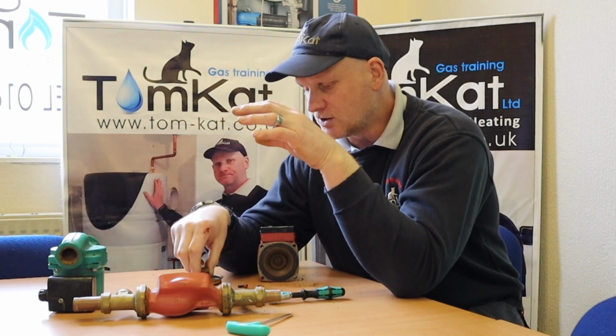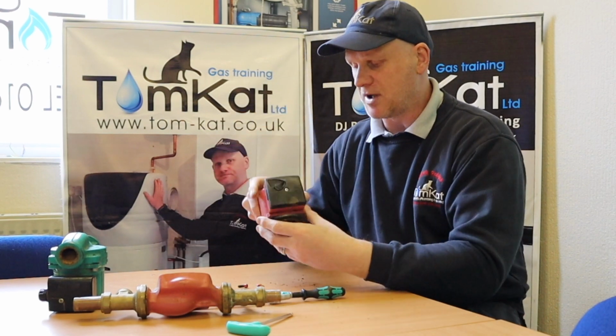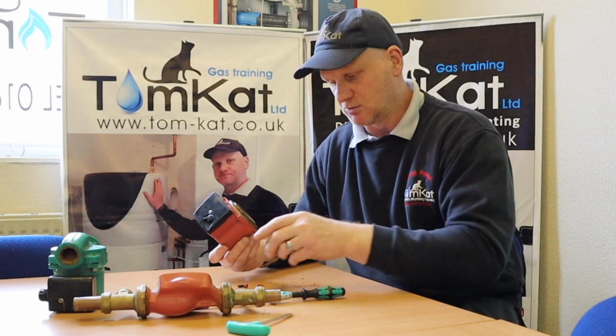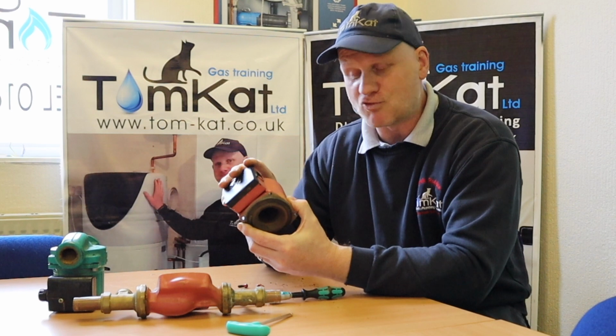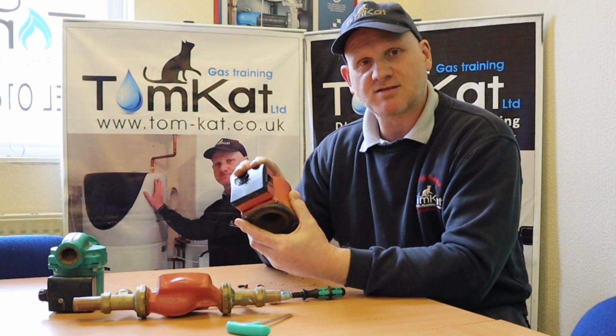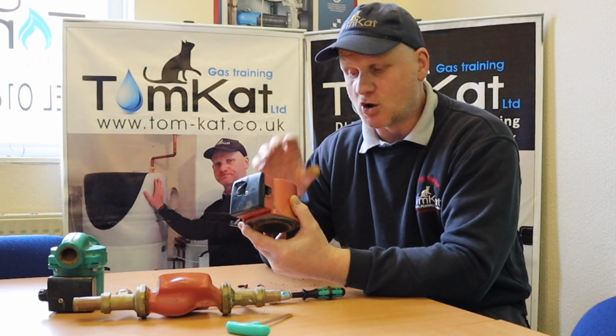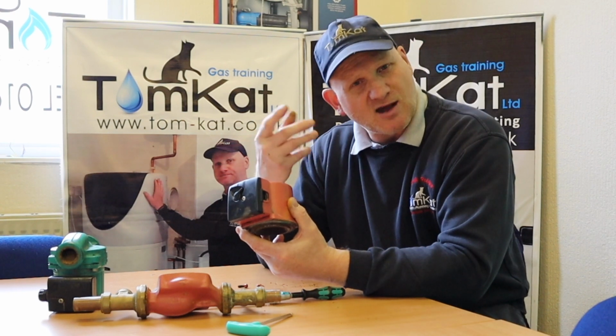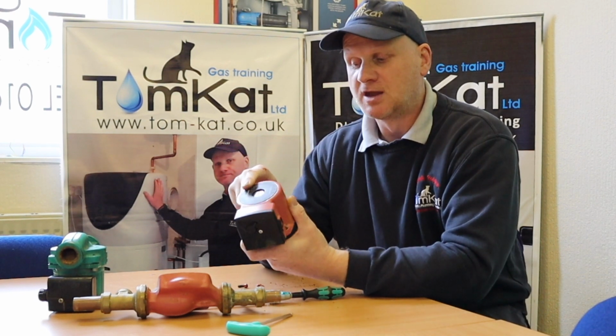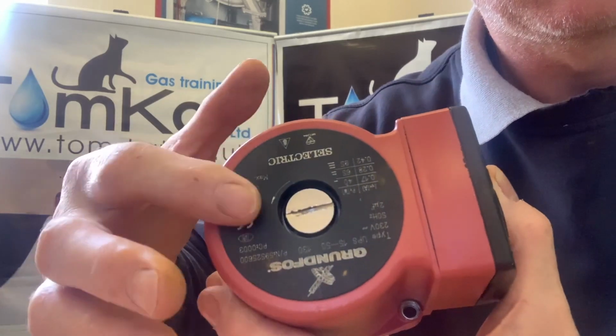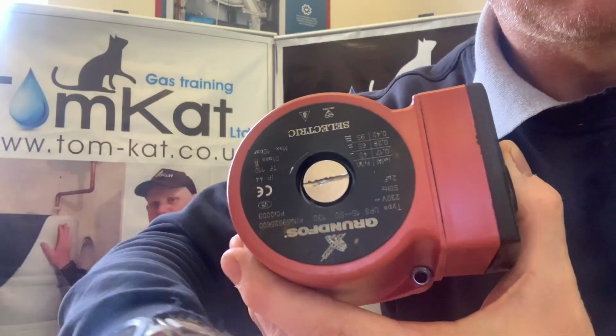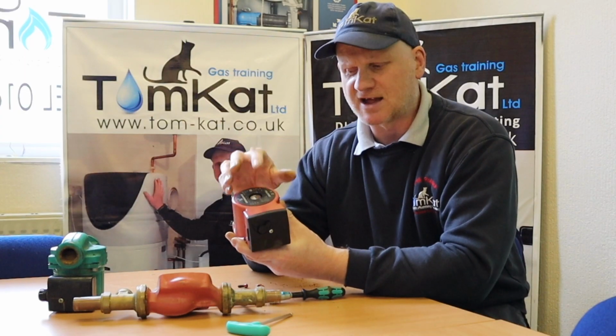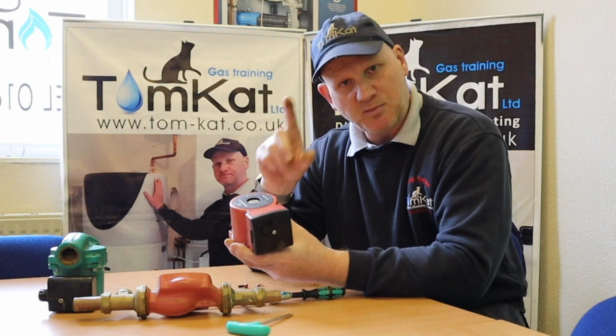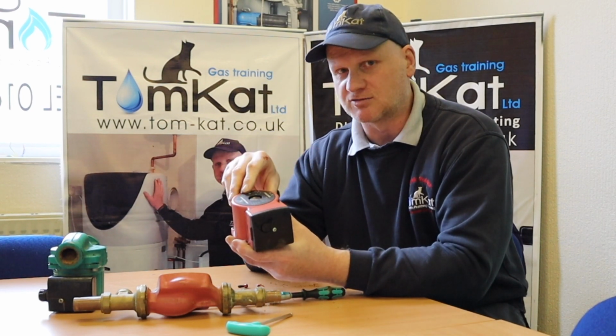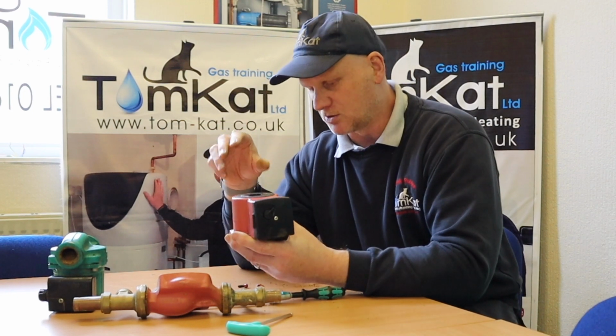So if you go to a central heating pump and that's the motor and this head is completely red hot, then there's every chance it's full of air because there's no water in there, and it's that air what's boiling as the pump's spinning. And you can actually release that air by undoing the screw on the end of there. That will release, so that's your bleed screw. On the new ERP pumps, there's no bleed screw. But again, we'll talk about those as we're going along.